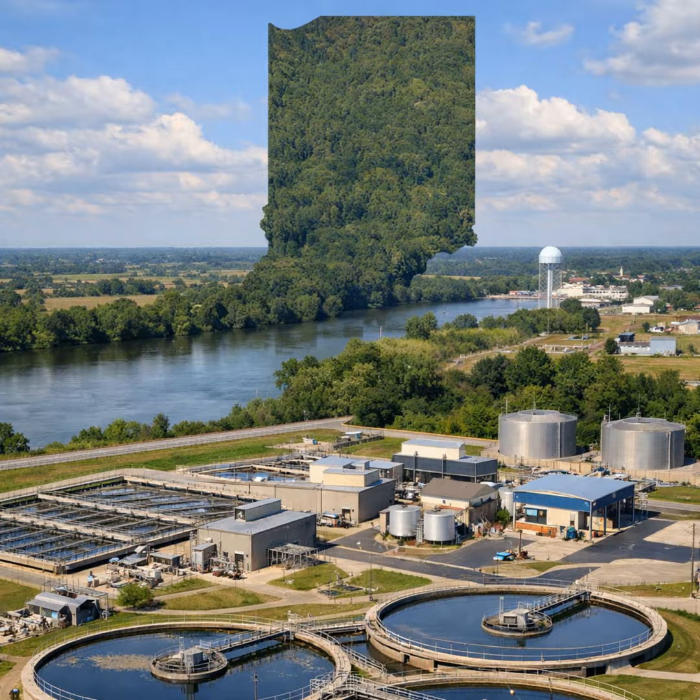Infiltration, the seepage of groundwater into a sewer system, including service connections. Seepage frequently occurs through defective or cracked pipes, pipe joints, connections, interceptor access risers and covers, or manhole walls.